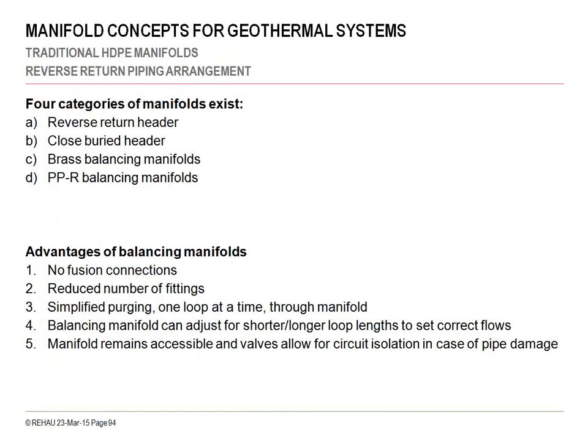It's just another advantage of that, in addition to being able to isolate down a single borehole, is that the flushing and purging of the system is simplified. We're doing one borehole at a time as opposed to an entire circuit, and it's not unusual in commercial applications in a circuit of HDPE pipe or reverse return headering to have as many as 8, 10, 12 boreholes on that circuit. If there's ever a leak in that circuit, you can isolate it down to that circuit, but you don't know which borehole it is, and then you go digging up and start looking for it, hoping that it's in the horizontal fusion and not in one of the boreholes.